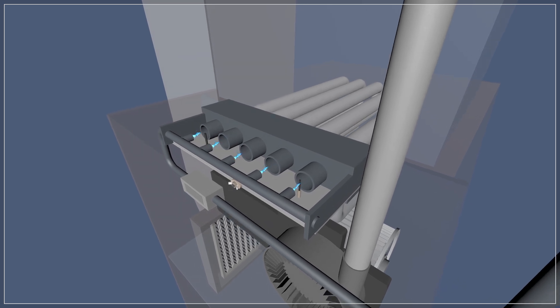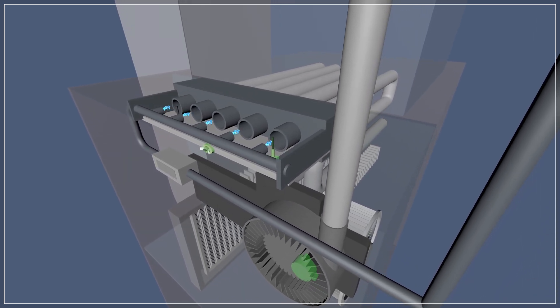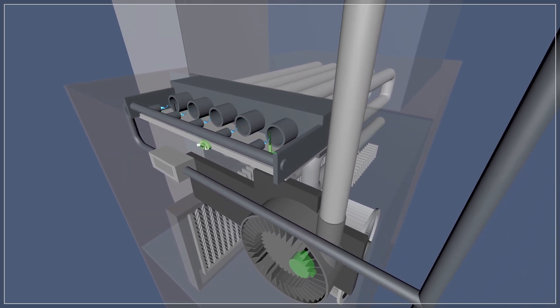Modern furnaces have a set of safety switches that shut down the furnace when the system is compromised. If a switch is tripped, it will cause the furnace to lock out. The furnace will attempt ignition several times before going into a hard lockout for up to an hour. Every time a lockout happens, the furnace will use flashing lights as codes to identify the source of the shutdown. These codes are unique to each model, so check your furnace manual to see what each code means.